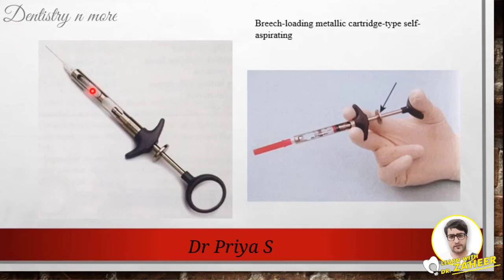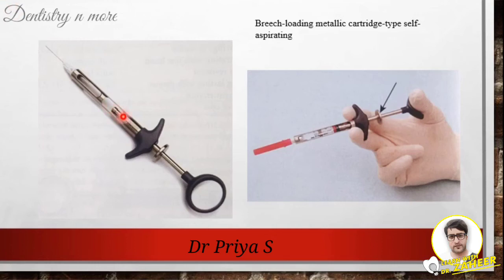The positive pressure created within the cartridge, which is then converted into negative pressure for aspiration, can be produced by the metallic plunger alone or by pressure from the thumb ring. It is found that the thumb ring produces twice as much negative pressure as the plunger shaft. The use of a self-aspirating dental syringe permits easy performance of multiple aspirations throughout the period of local anesthetic deposition.